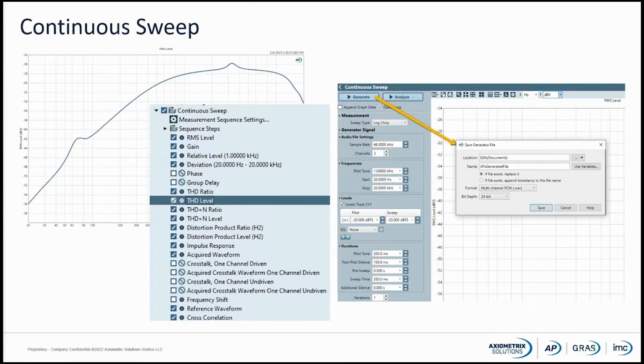The continuous sweep measurement has a save generator file feature for open loop testing, and like the stepped sweep, provides response and additional results. The major difference between these two measurements is the speed of operation. Stepped sweeps can run for 30 seconds or more, while continuous sweeps are generally completed in less than 1 second.